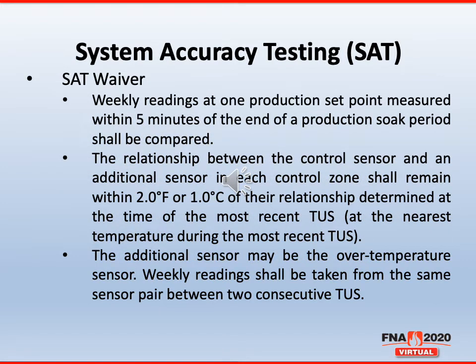Furthermore, the weekly readings that are required shall be done at one production set point measured within 5 minutes of the end of a production soak period and shall be compared. That relationship between the control sensor and the additional sensor in each control zone shall remain within 2 degrees Fahrenheit or 1 degree Celsius of the relationship determined at the time of the most recent TUS and at the nearest temperature during the most recent TUS. The additional sensor may be the overtemp sensor. Those weekly readings shall be taken from the same sensor pair between 2 consecutive TUSs.